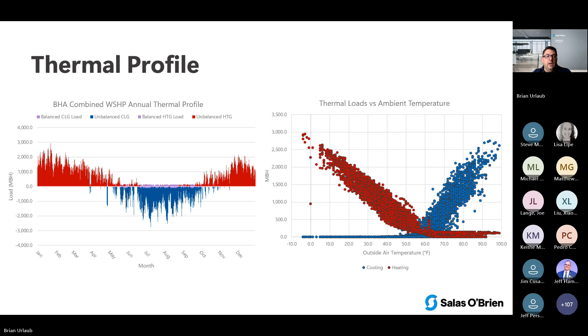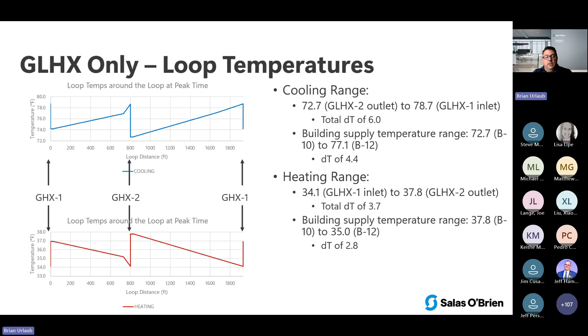So we had a delta T of 2, a delta T of 4, a delta T of 6, and really tried to figure out what's the optimization there to minimize pipe size, pumps, costs, and pump energy. Again, going through that iteration is critical to making these projects viable, looking at your thermal assets and how they stack up.